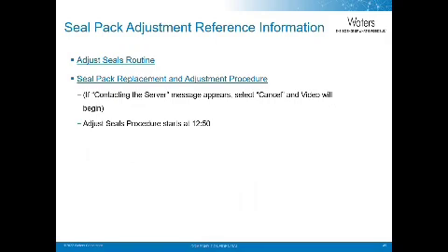Seal pack adjustment is also part of the PM. The first hyperlink, Adjust Seals Routine, links to the Service Assist procedure. The second link is to the service video of the seal pack replacement. If when viewing the video you receive a message saying contacting the server, select Cancel and the video will begin. The Adjust Seals procedure starts at 12:50 minutes.